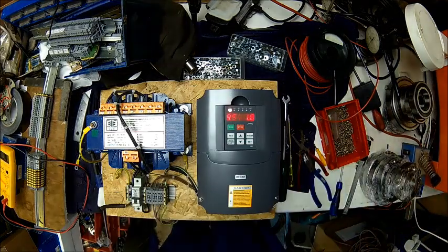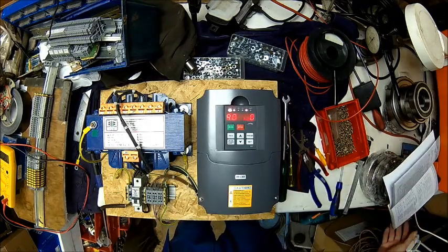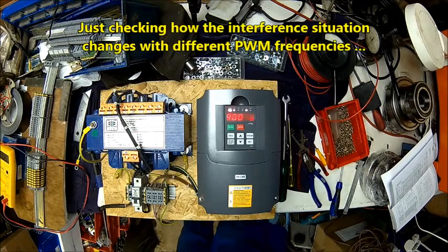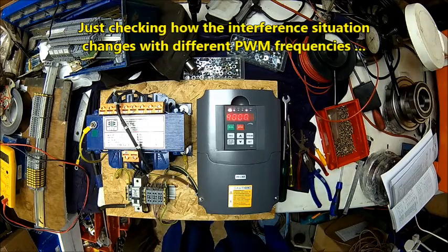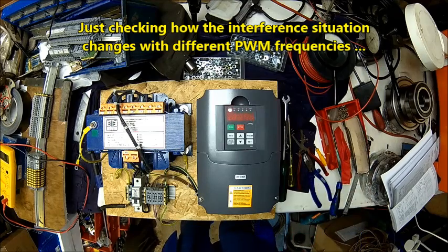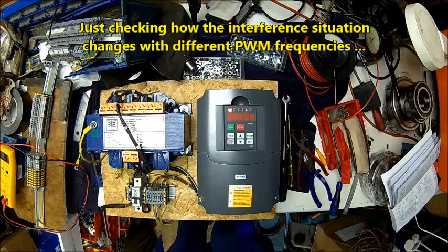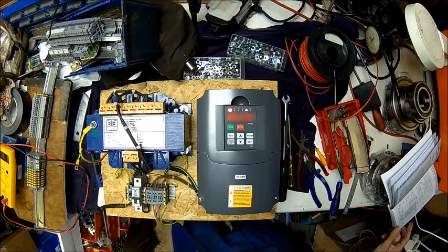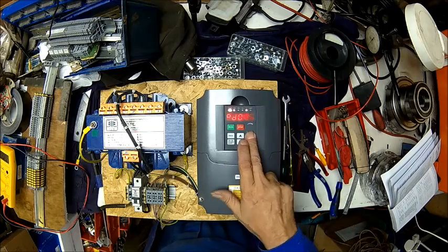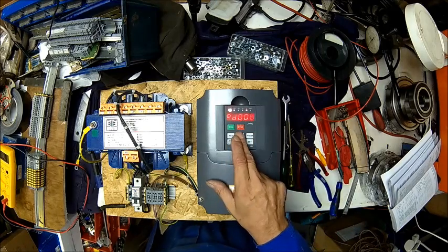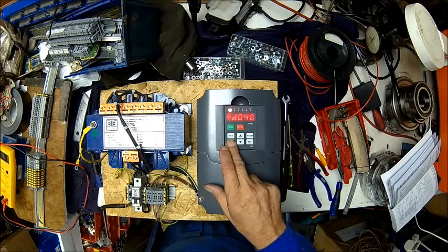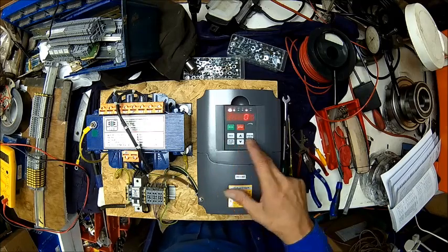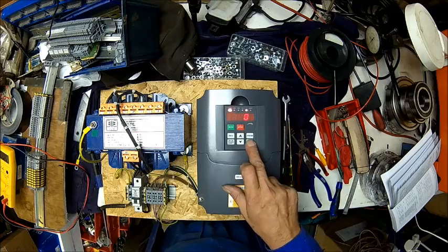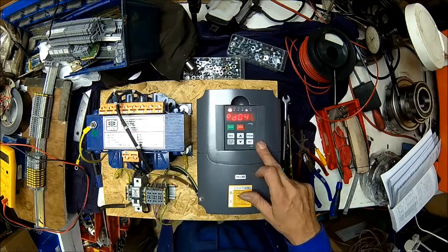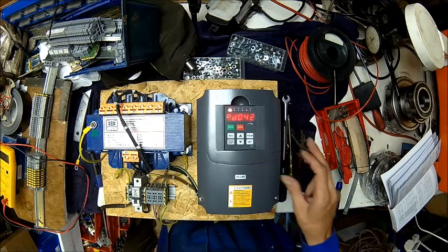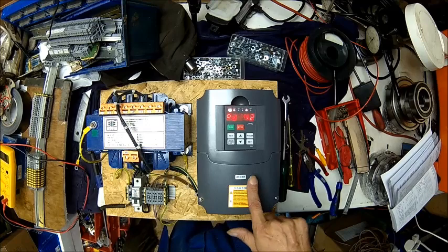The problem is if you increase the switching frequency of the inverter, you need to downrate it, because I think it only does full power at 3 kilohertz, and that's when you hear the whistling. If you go higher with the switching frequency, it's actually parameter 41. The problem is that you're producing even more interference. I set it to 4 already, make it 6 kilohertz. You can crank it up to 15. The problem is that the thing makes even more noise and you cannot pull the 4 kilowatts anymore.